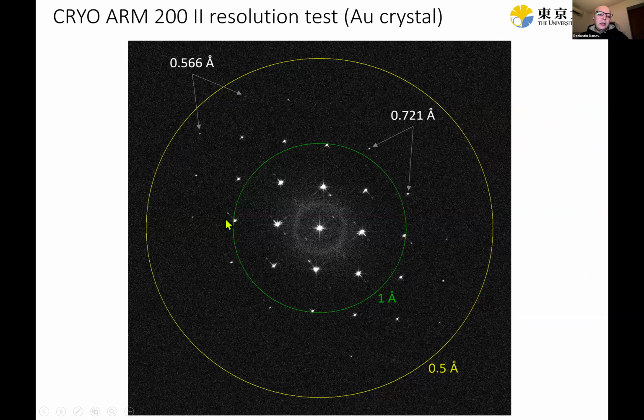Now, to test the machine initially, we used an oriented single crystal gold sample. We took some images, and here you see the Fourier transform of one of the best images. It shows spots along the tilt axis. So the tilt axis is something like this. I don't have it marked here because I don't know exactly where the tilt axis is. Along the tilt axis, we see spots up to 0.566 angstrom resolution, and perpendicular to the tilt axis, they go up to 0.7. So in all directions, the resolution goes beyond 1 angstrom, which is I think very satisfactory for cryo-EM applications where we don't usually reach close to 1 angstrom.